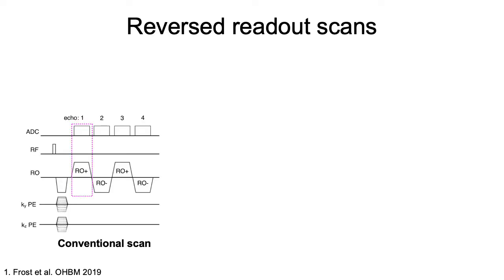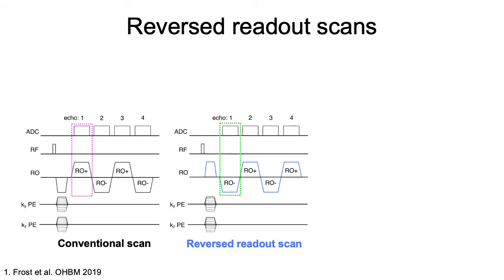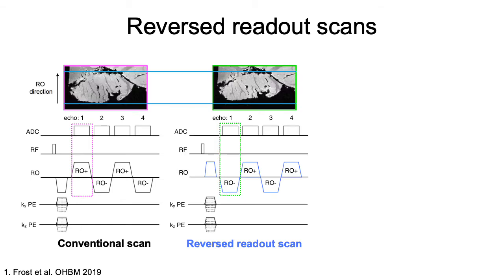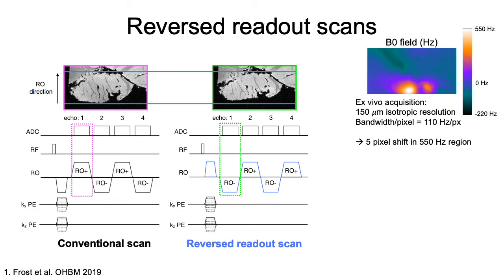If we look at the first echo of a normal multi-echo sequence and compare with a reverse polarity sequence, we see that the resulting images have opposite distortion in the readout direction. This was an ex vivo scan with 110 Hz per pixel bandwidth, so in a 550 Hz region of off-resonance we get a 5 pixel shift.